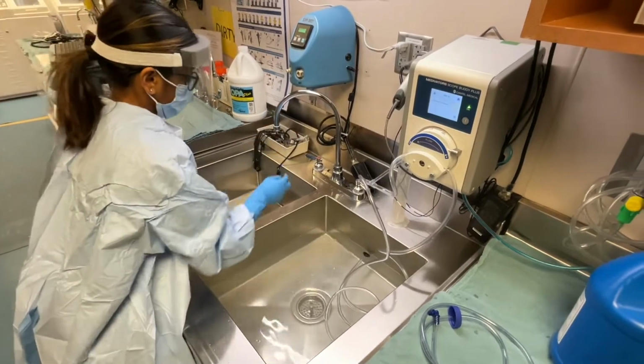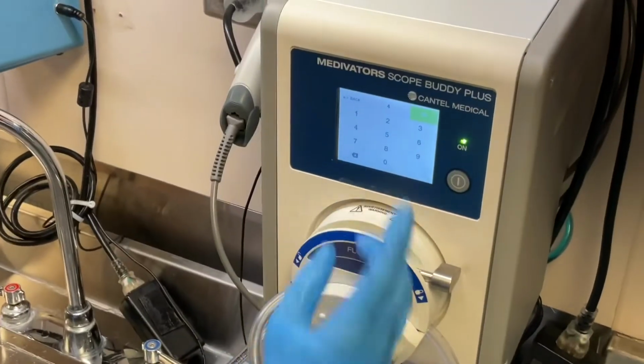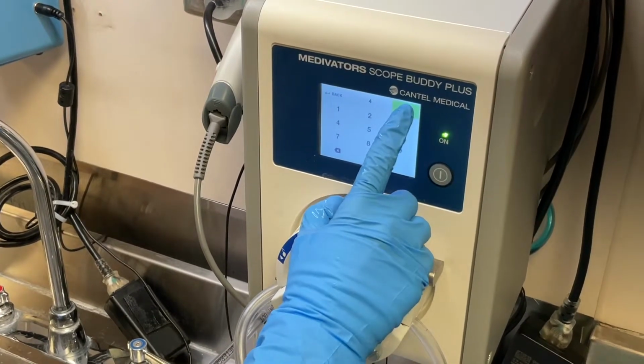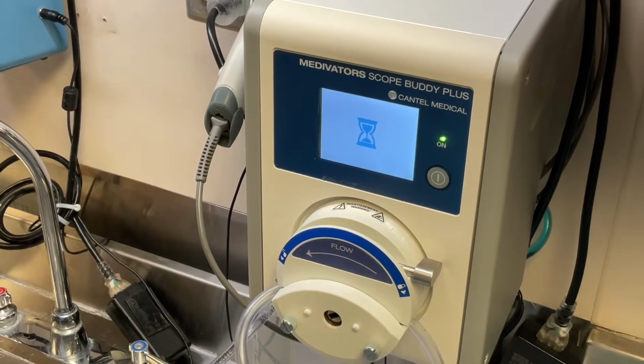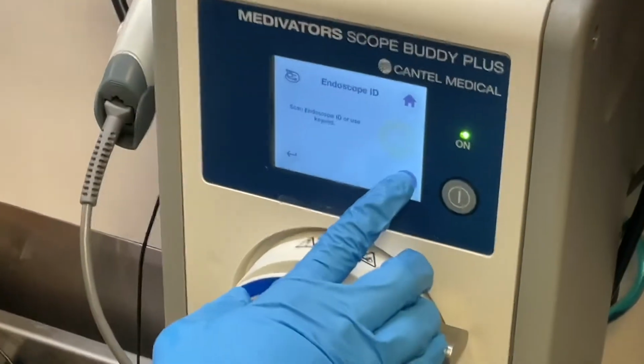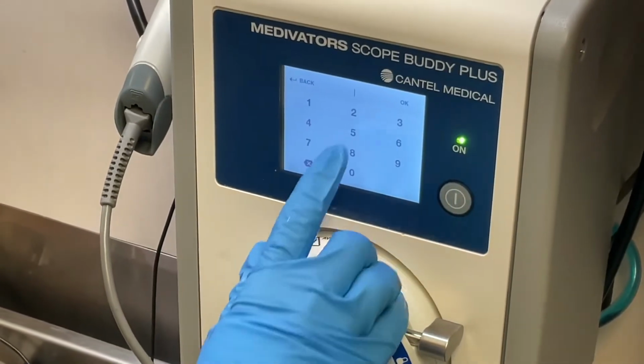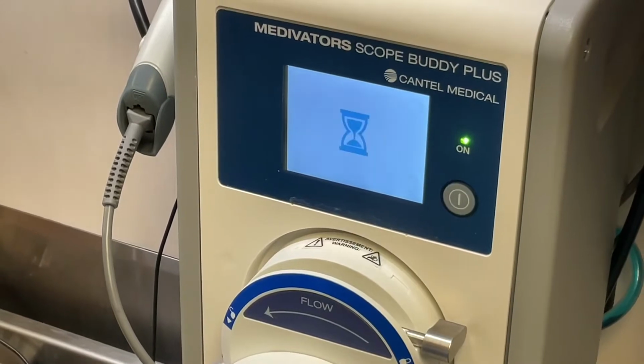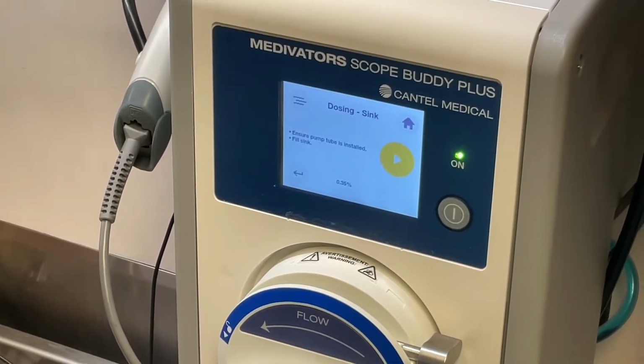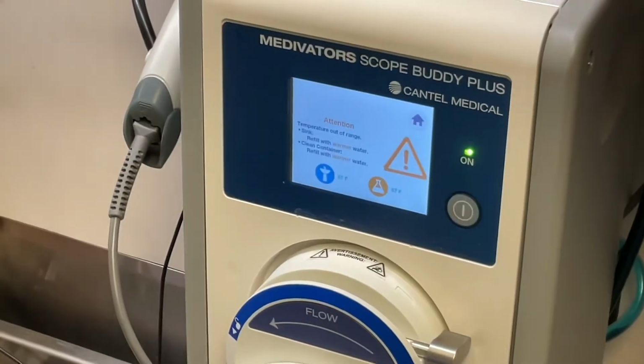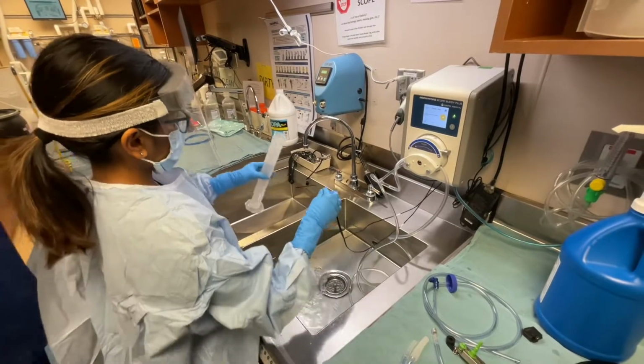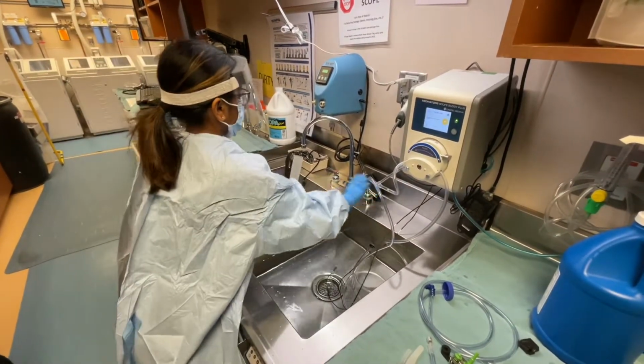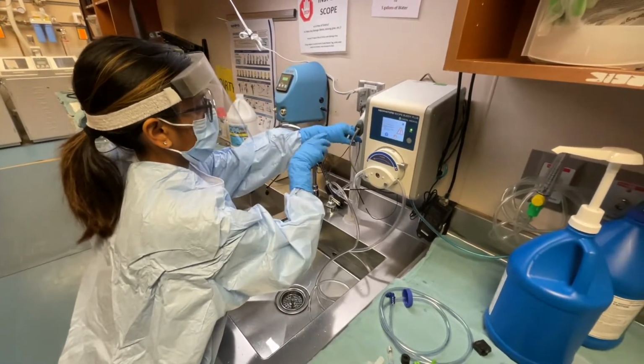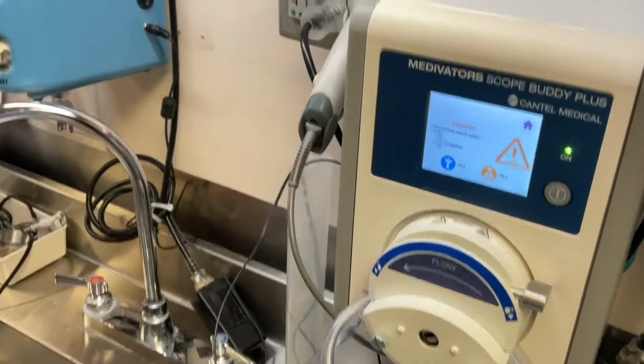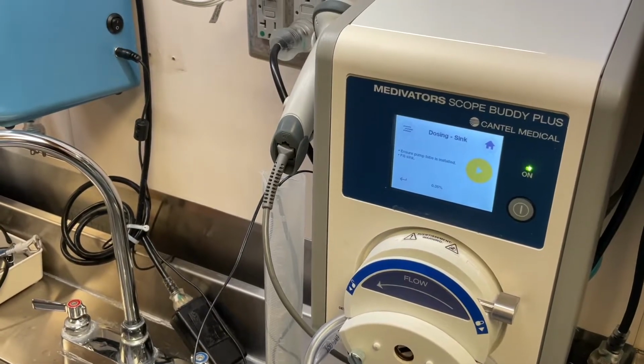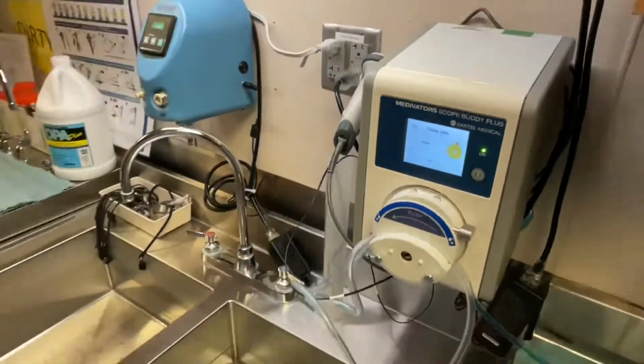Put in user ID. This will be dependent on whether it's a nurse or a tech. Put in Scope ID. Dose sink to appropriate amount of detergent. If your temperature probes are not at the correct temperature, you will not be able to clean your scope. You can add hot or cold water until you reach the desired temperature on the screen. It'll take a few moments for your temperatures to regulate. Then proceed. Dose sink.